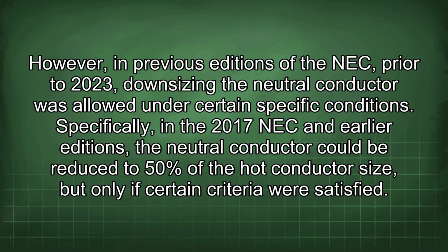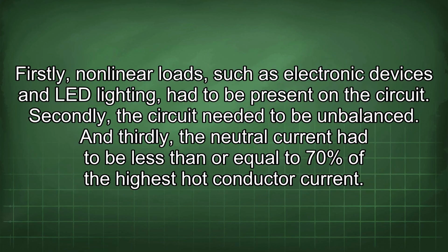conditions. Specifically, in the 2017 NEC and earlier editions, the neutral conductor could be reduced to 50% of a hot conductor size, but only if certain criteria were satisfied. Firstly, nonlinear loads, such as electronic devices and LED lighting, had to be present on the circuit. Secondly, the circuit needed to be unbalanced. And thirdly, the neutral current had to be less than or equal to 70% of the highest hot conductor current.